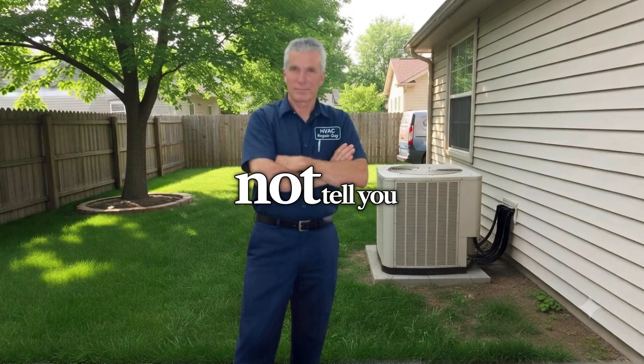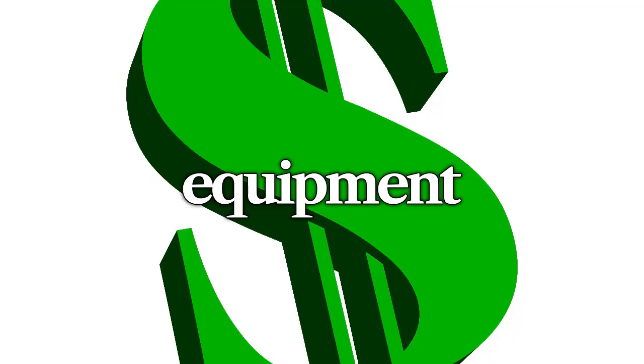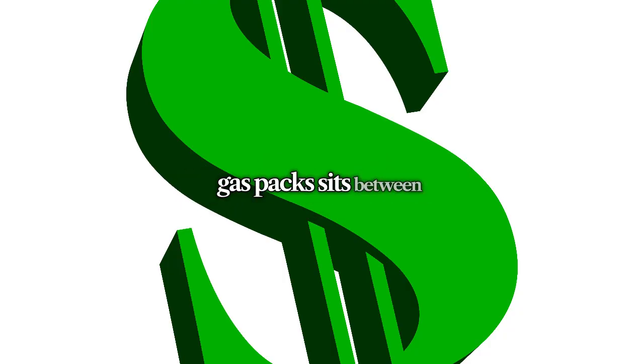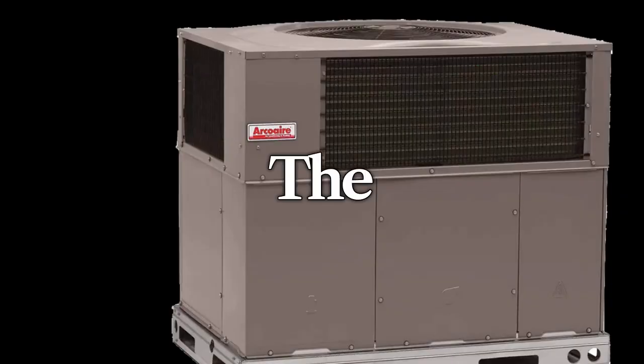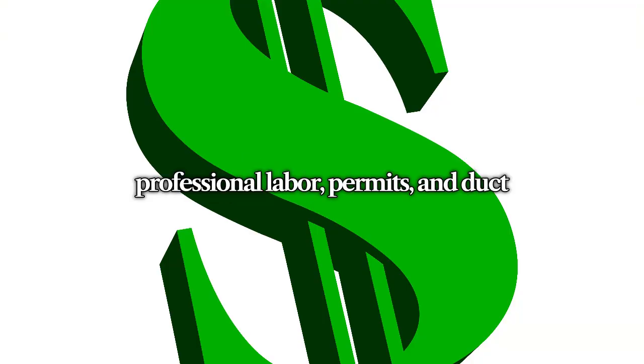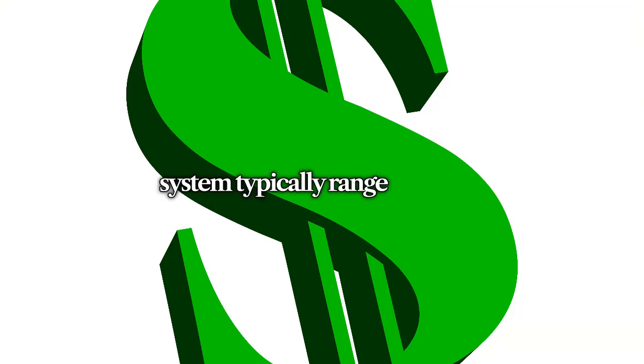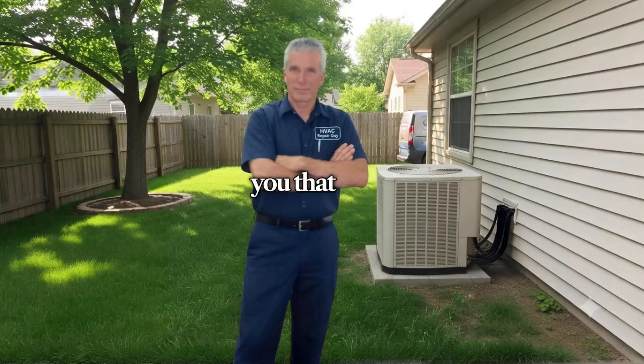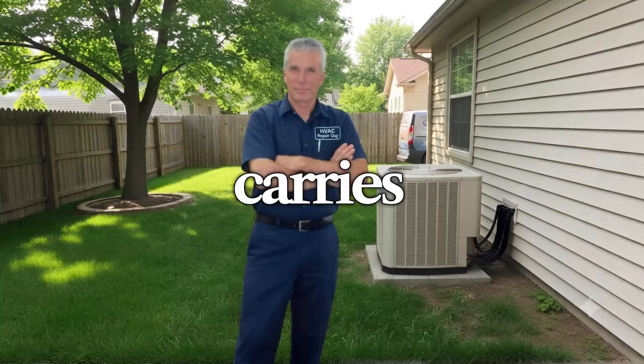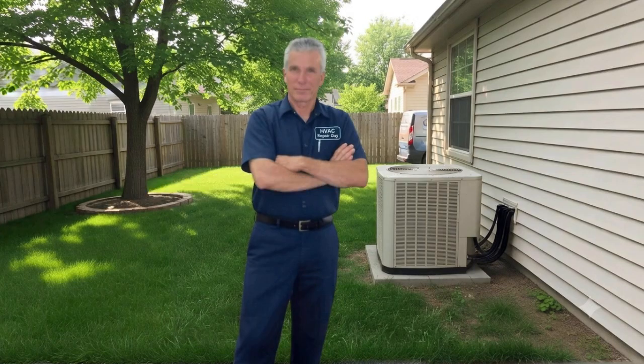What the brochure will not tell you is that installation quality matters far more than the name stamped on the cabinet access door. When looking at current market pricing, the equipment cost alone for these 3-ton baseline gas packs sits between $4,800 and $5,800. The Arcoaire PGB4 lists around $5,190 to $5,770 for the unit itself. The American Standard Silver 13.4 equipment pricing ranges from $4,810 to $6,450 depending on the distributor. Once you factor in professional labor, permits, and duct transitions, total installed costs for either system typically range between $7,000 and $10,000. Arcoaire gives you that extra unit replacement warranty coverage up front, while American Standard carries a slight equipment premium for its superior louvered cabinet protection and long-standing build reputation.